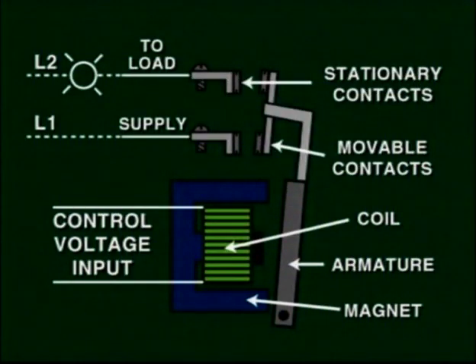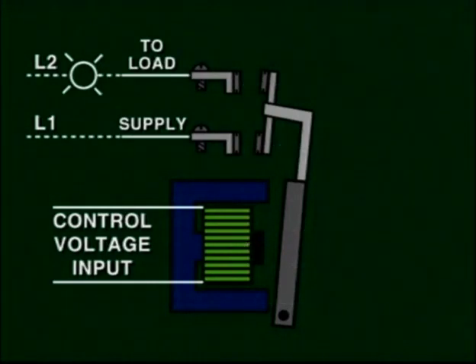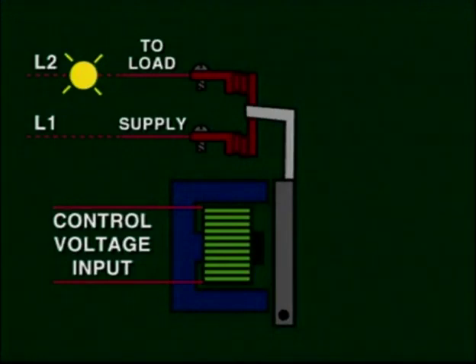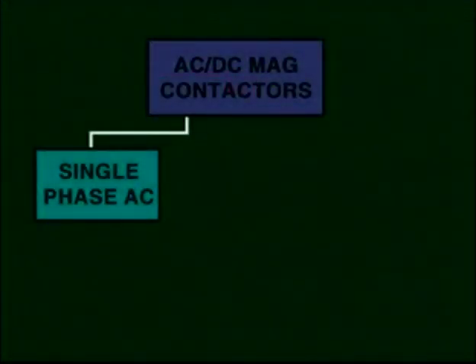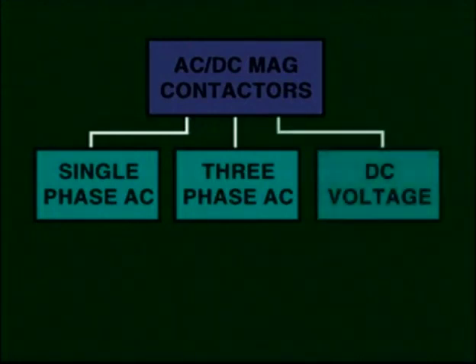Although there are several types of contactor assembly designs, all of them operate in a very similar manner. When voltage is applied to the magnetic coil, the armature is attracted and forces the movable contacts to make connection with the stationary contacts. Magnetic contactors are available for single-phase and three-phase AC voltages, as well as for DC voltages. Contactors for each of these three categories are rated according to NEMA, to specify the size of the load that they can handle safely by each contact in the contactor. The sizes range from 00 to 9, according to the horsepower of the load and the voltage being switched.